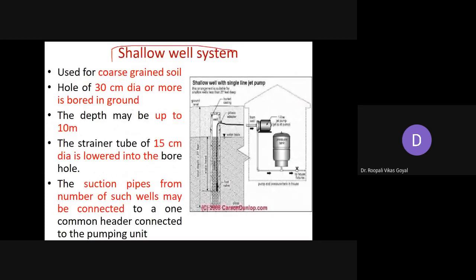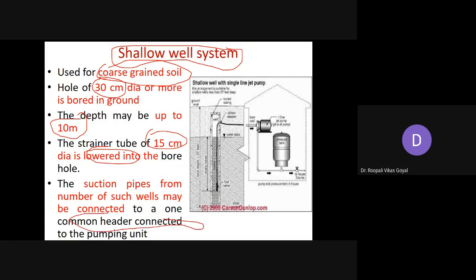Next is the shallow well system. Similar to the deep well, wells are constructed at shallow depth. It is used for coarse-grained soil. A hole of 30 centimeter diameter or more is bored in the ground to a depth of up to 10 meters. A strainer tube of 15 centimeter diameter is lowered into the bore hole. Suction pipes from a number of such wells are connected to one common header pipe connected with the pumping unit.